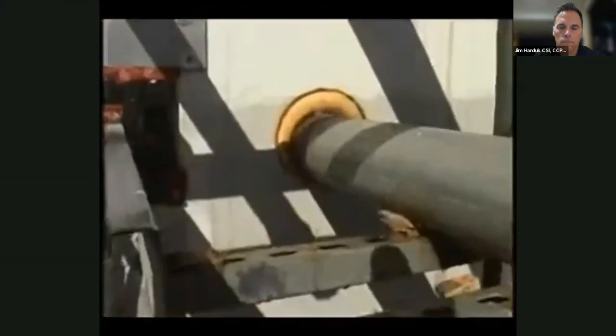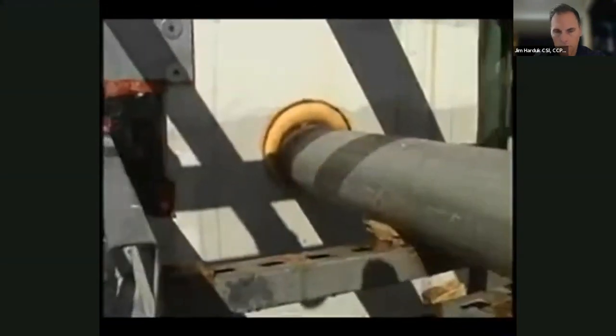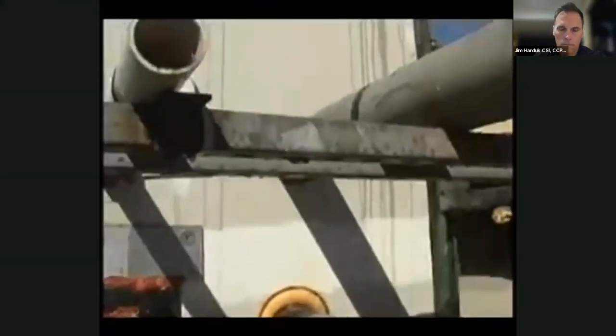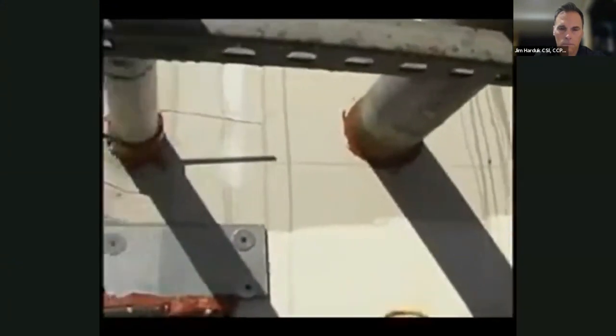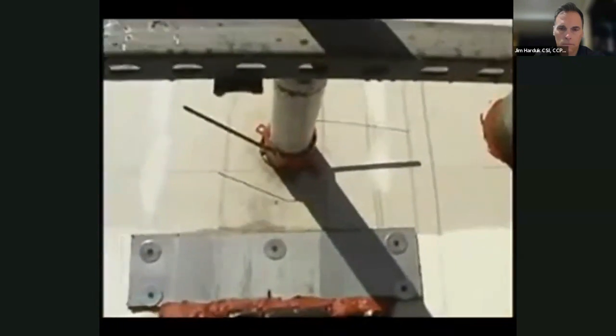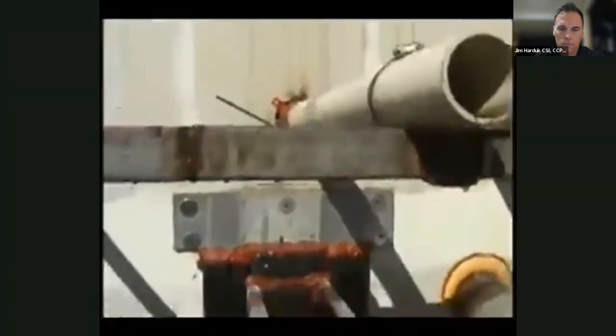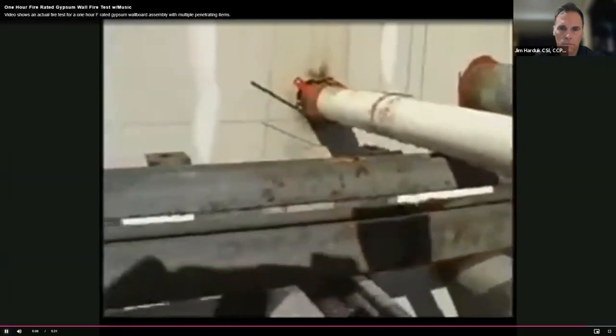To achieve an hourly F rating, there cannot be any flame propagation through the wall or the penetration on the non-fire side of the assembly, and you must pass the hose stream test, meaning there cannot be any dislodgement of firestop material at the penetration.